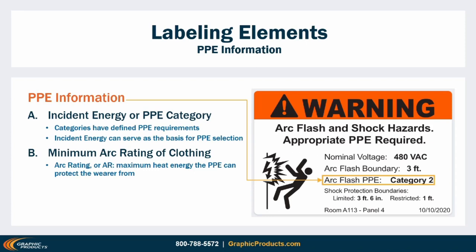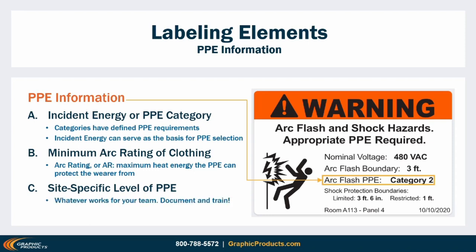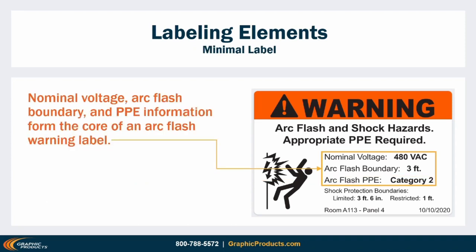Experts often recommend the minimum arc rating approach because it simplifies the job for the worker on site and allows informed decisions based on what equipment is actually available in the workplace. Finally, there's a catch-all option for any other system that works well for your facility — some common choices include an itemized list of required PPE elements or a company-defined category system like a color code. As long as the system is clearly identified, documented, and your workers are trained to understand it, you have a lot of leeway. Those details — nominal voltage, arc flash boundary, and PPE — form the core of an arc flash warning label.